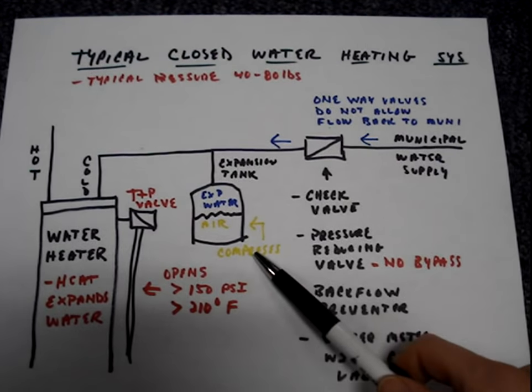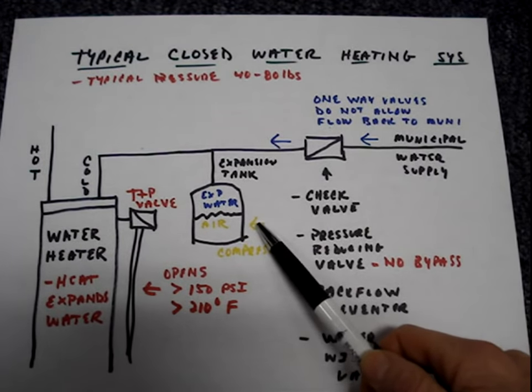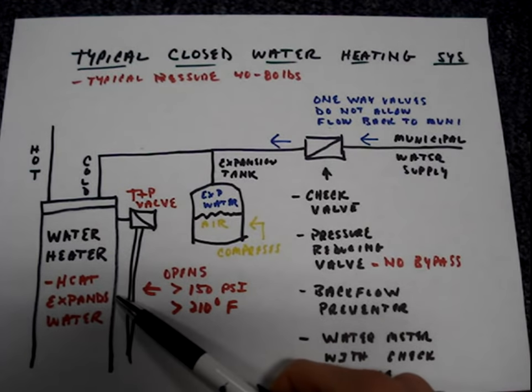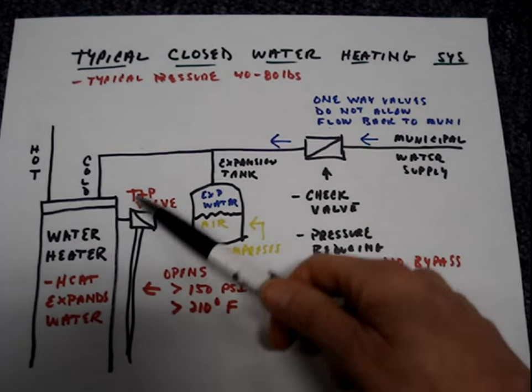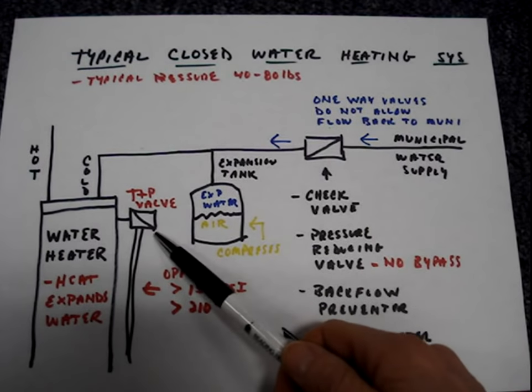If the expansion tank doesn't have any air in it, or a closed water heating system doesn't have an expansion tank, whenever there is thermal expansion and the pressure in the system increases above 150 psi, then the valve will open.